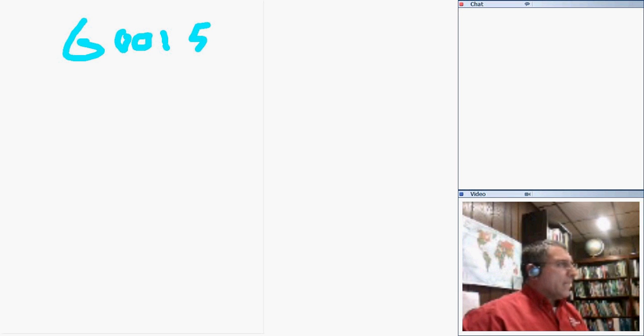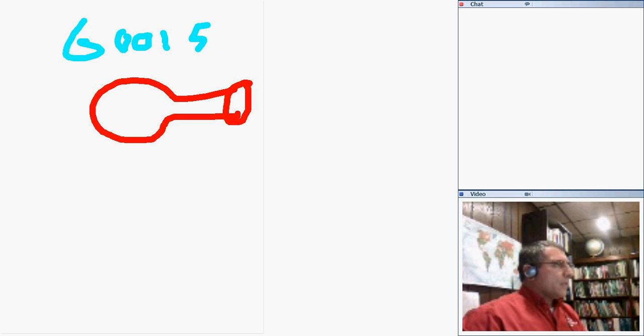We use it this way. Suppose you have a 600 to 5 CT, and you want to make it more sensitive. 600 to 5 is not as sensitive. Suppose I want to make it more sensitive. You know what they do? You loop it. So if I loop it one loop, here's my meter, and here's my conductor.